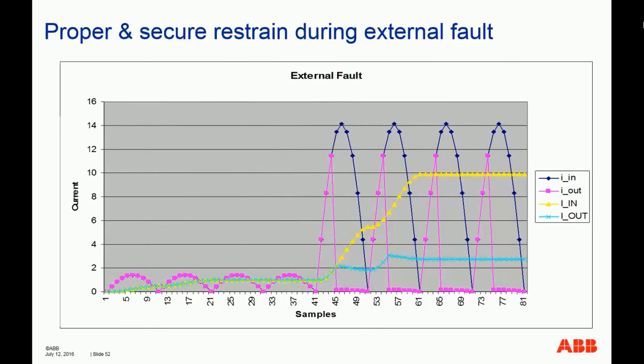And next, let's look at how the relay operates for an external fault. Again, during the external fault at the beginning, everything is stable. You have normal load flow. Okay, everybody's happy. But as soon as the fault happens outside of the protection zone of the bus protection relay, you can see at the very beginning, and this is critical, the relay needs a minimum amount of time to see that a fault happened.